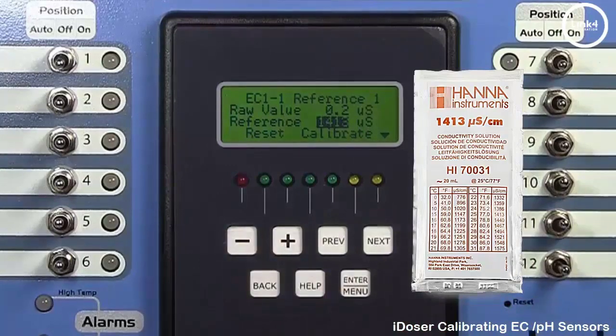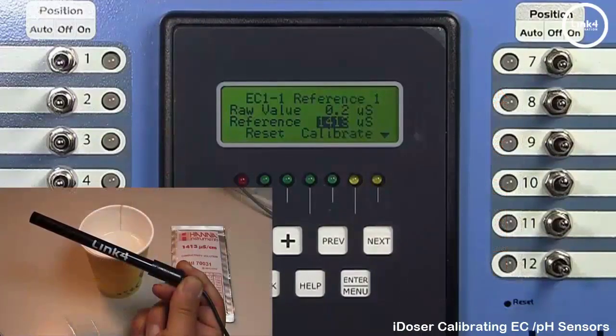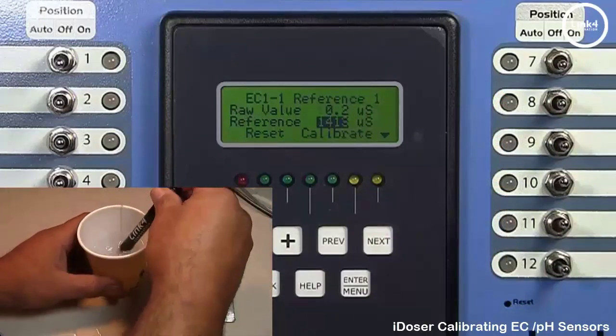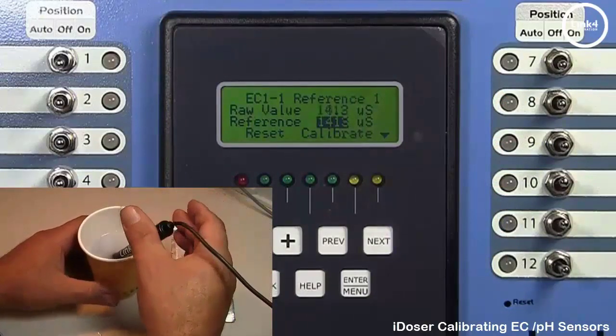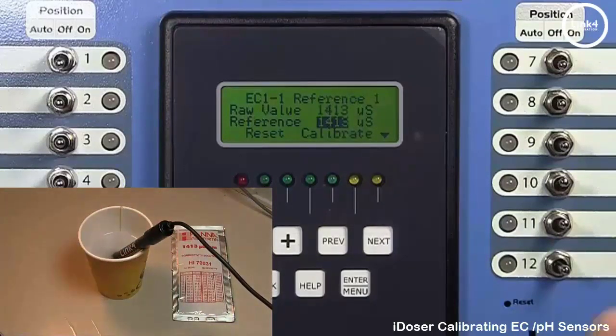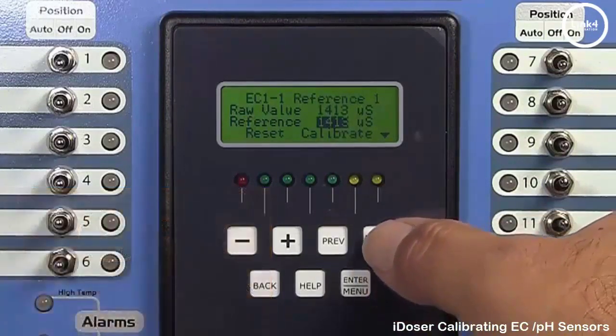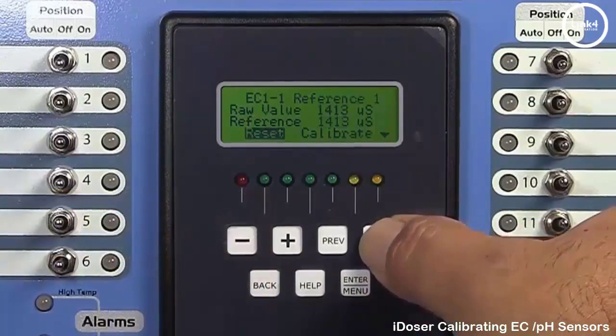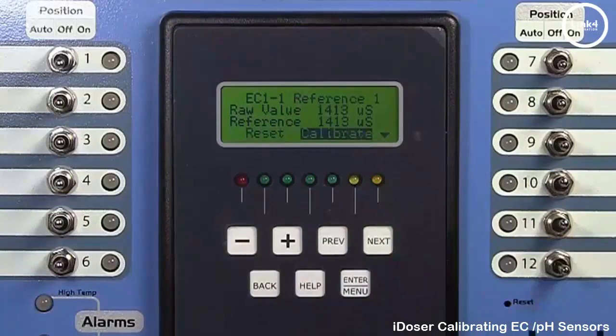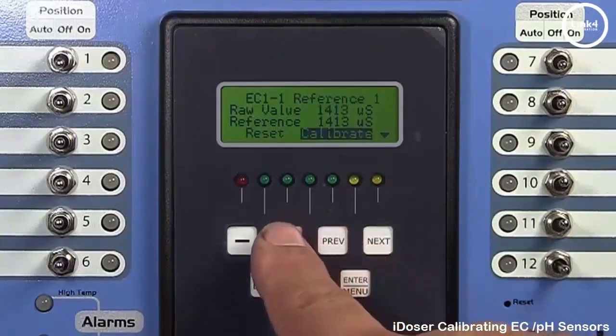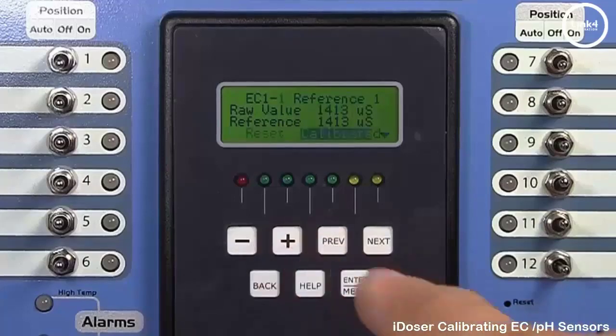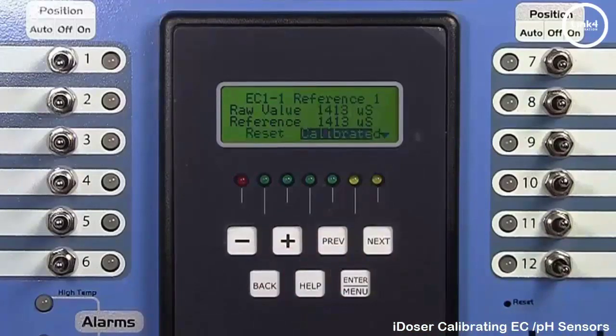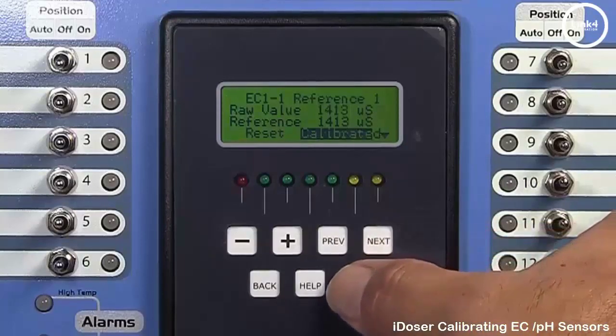Next, we will open the pouch of the conductivity solution and we will go ahead and put our EC sensor into the solution. We will stir and wait for a raw value to settle. Once settled, we will go ahead and hit Next to highlight Calibrate. Once you have Calibrate highlighted, simply hit plus to calibrate this sensor. And once the sensor says calibrated, the EC probe has in fact been calibrated. So go ahead and hit Next.